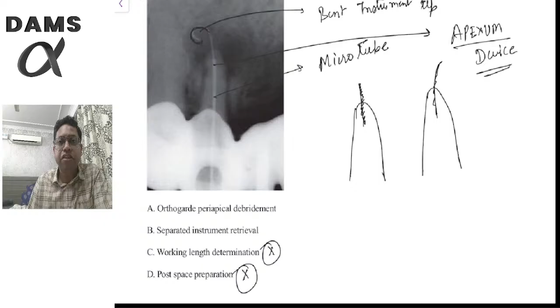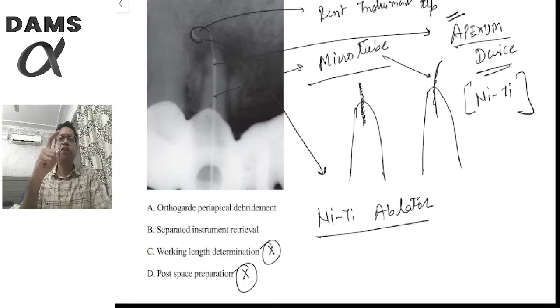An Apexum device is based upon nickel titanium. Two things are there. This is a microtube made up of nickel titanium, and this is a nickel titanium ablator. When this nickel titanium ablator is passed through the microtube into the periapical tissues, because of its shape memory, it assumes a bent shape and then it is rotated. So it mixes and minces the periapical lesion like a blade of a mixer, and it can then be flushed copiously to drain it out from the root canals.